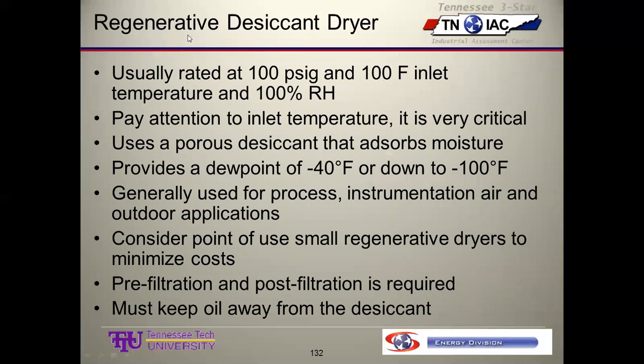Regenerative means that the way these are set up, they have twin towers. Both of the towers or tanks are full of desiccant. So we will dry on one tower, and we will regenerate, or drive the moisture out of, the second tower while the first tower is drying. And then on some sort of an interval, we switch. They just keep switching back and forth so that the dryer can continue to produce the dry compressed air that the system needs.